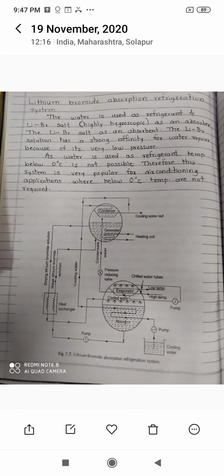As water is used as a refrigerant, temperatures below 0 degrees Celsius are not possible with this system. Therefore, this system is very popular for air conditioning applications, where temperatures below 0 degrees Celsius are not required. With this system we cannot decrease the temperature below 0 degrees Celsius, as water is used as a refrigerant.